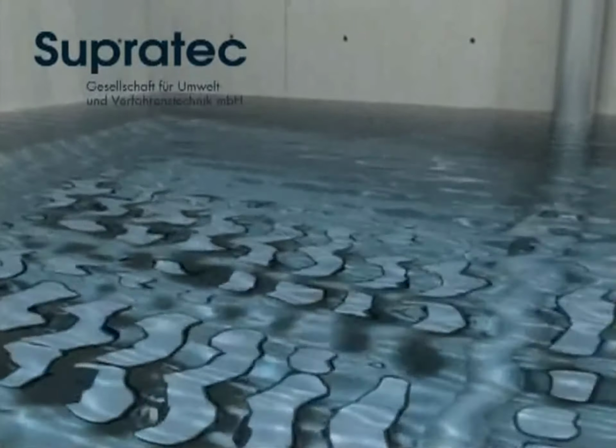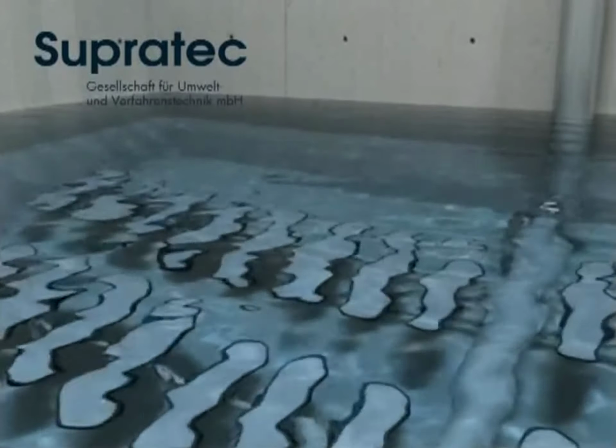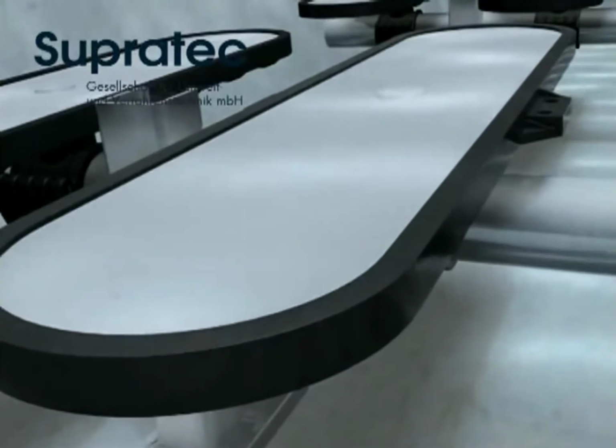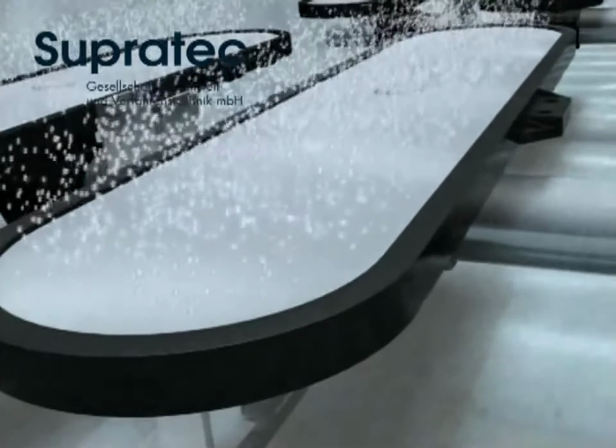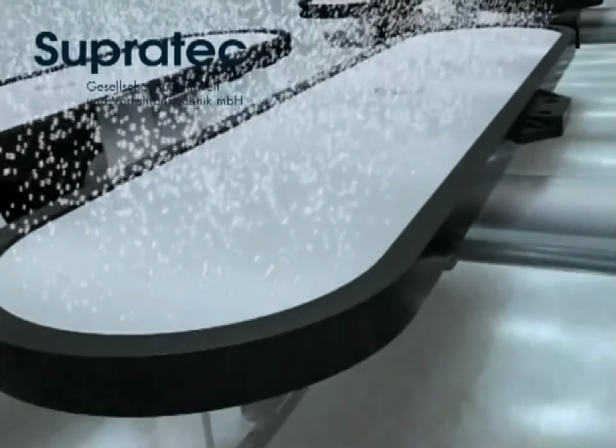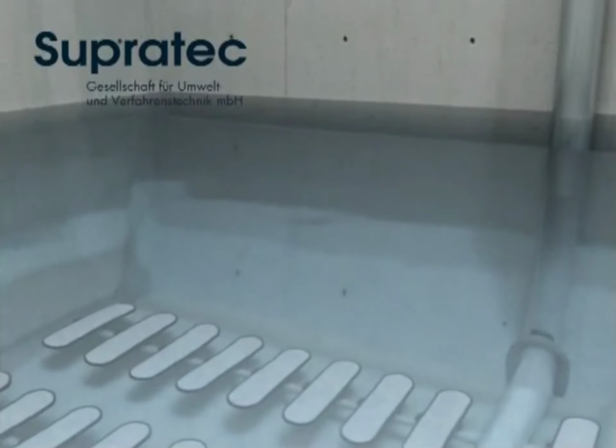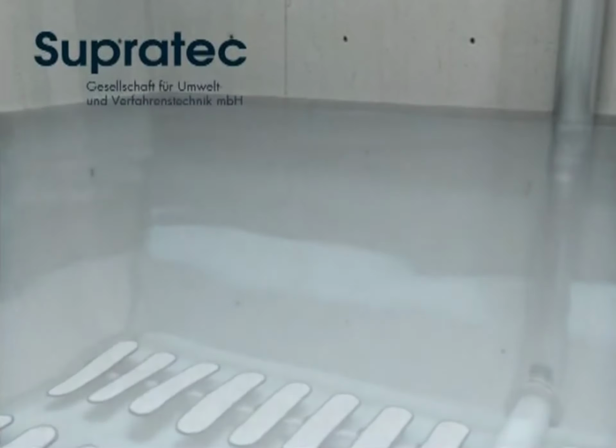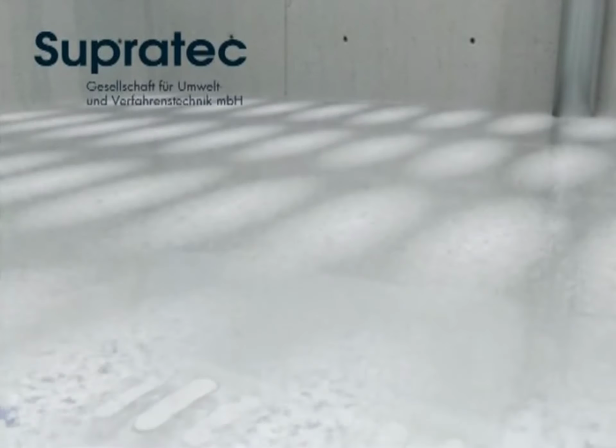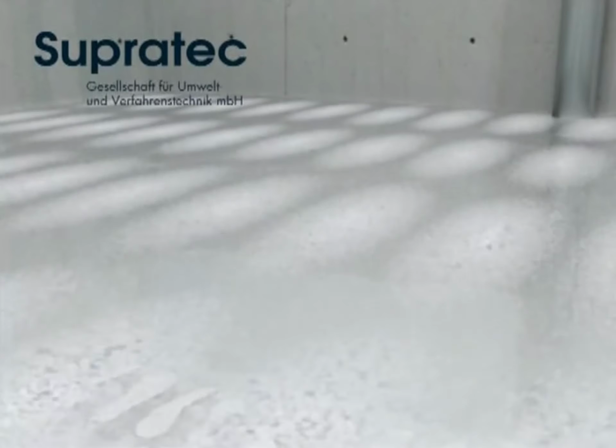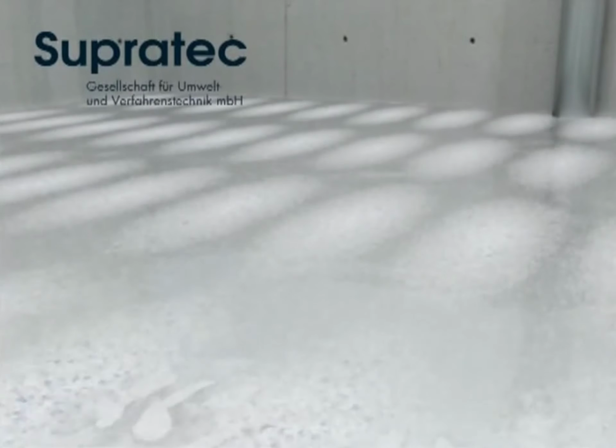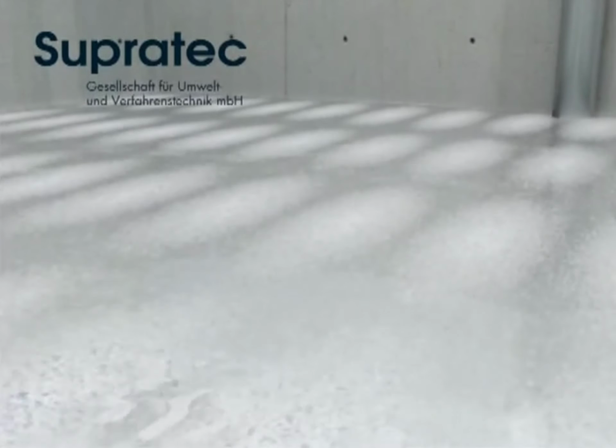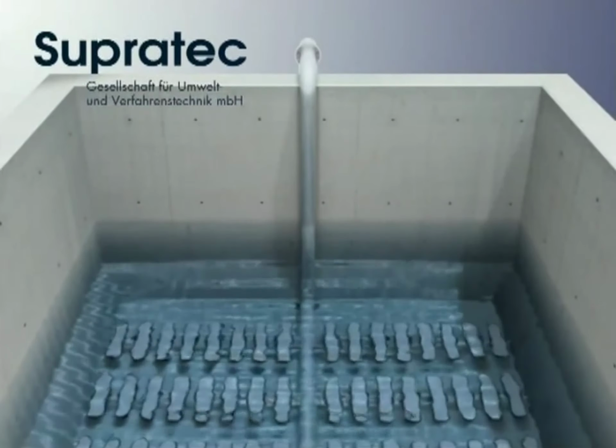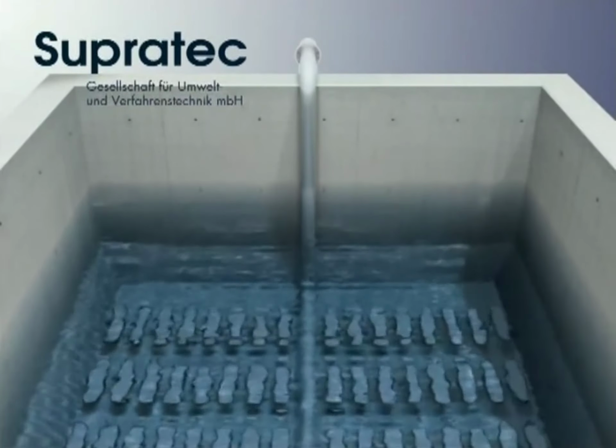A trial run should be performed of at least 60 hours in duration at standard airflow volumes and with a minimum water covering of at least 100 centimeters. If this trial run is completed without problems, water can then be filled to the operating level.